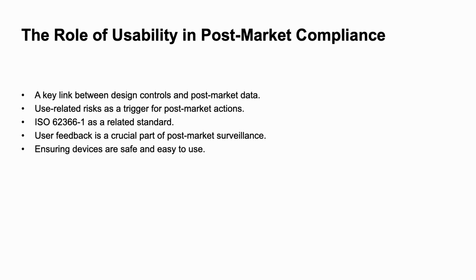Usability is a critical and often overlooked component of post-market compliance. A medical device may be technically perfect, but if it is difficult or confusing to use, it can pose a significant risk to patient safety. The QMS must have a process for addressing use-related risks, which is a key link between design controls and post-market data. For example, if a manufacturer receives a number of complaints that a surgical device is difficult to use, this could be a use-related risk that needs to be investigated. A manufacturer can use standards like ISO 62366-1 for usability engineering to design a device that is safe and intuitive to use.